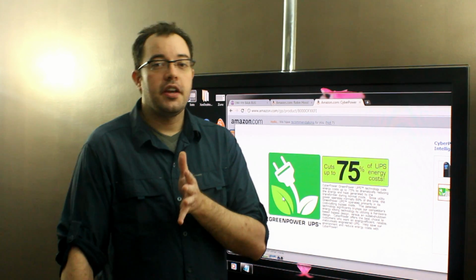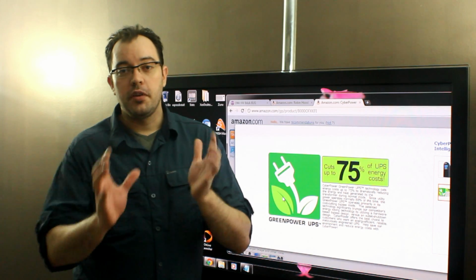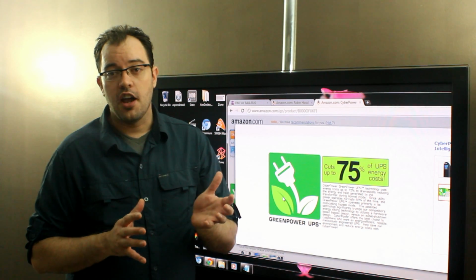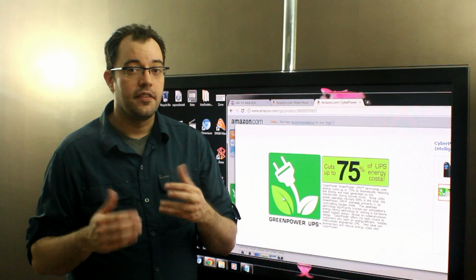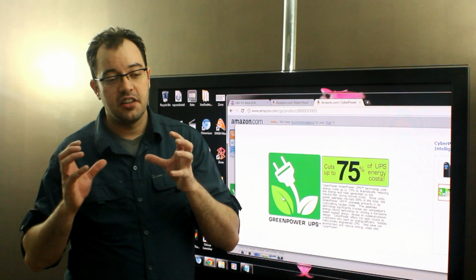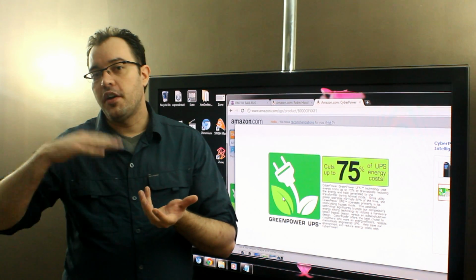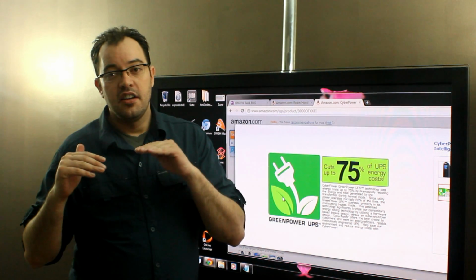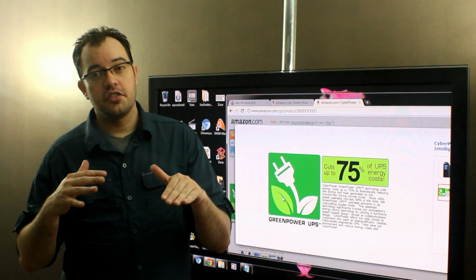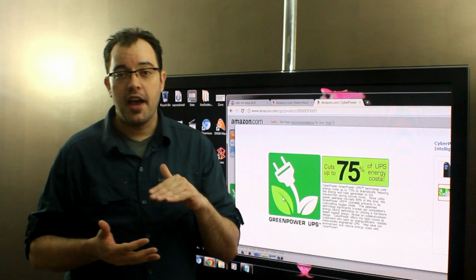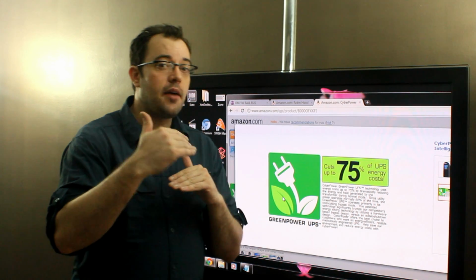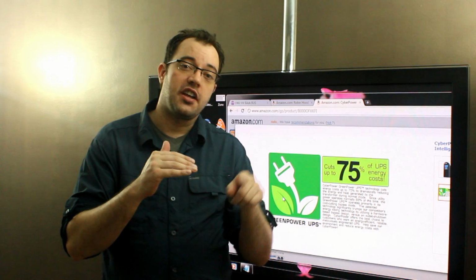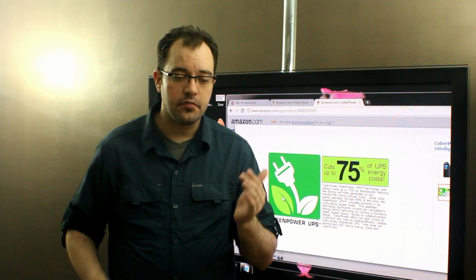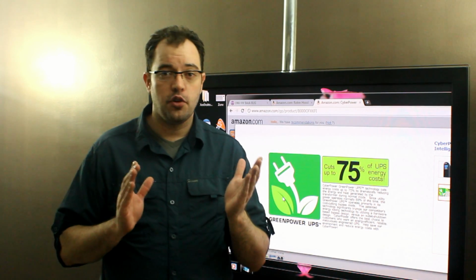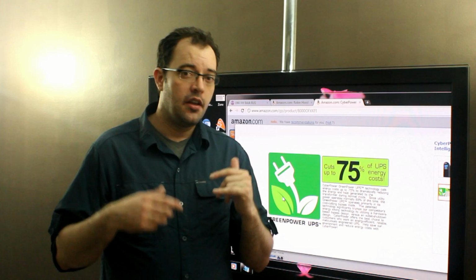When you're using a UPS, you've got to keep the UPS batteries charged all the time. If you're using it for power filtering, you're going through a transformer that's stepping the 120-ish volts coming in down to 12 volts or 6 volts for storing in the lead-acid batteries, then transforming that back up to 120 volts and applying a sine wave to it. Both of those transformers add inefficiencies.